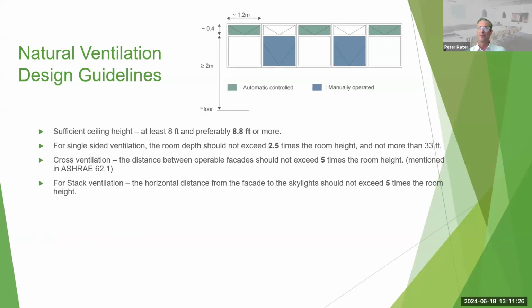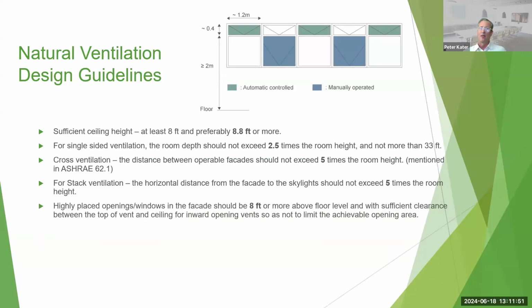The stack ventilation, the horizontal distance between the windows on the facade and the skylights, which exhaust the warmer air, shouldn't be more than 5 times the height of the room. So they should be aligned relatively closely in a horizontal distance, not more than 5 times the room height. Highly placed windows in the facade should be at least 8 feet or more above the floor, with sufficient clearance between the top of the vent and the ceiling. This is for inward opening bottom hung vents, so that you don't obstruct or limit the usable opening area which air flows in or out through.